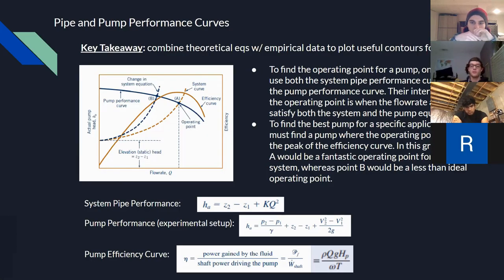To find the operating point for a pump, we must find the intersection of the pump performance curve and the pipe system performance curve. This is the operating point, as at this point both the system and the pump will give the same head rise for a specific flow rate. Once this operating point is found, to find the best pump for a specific flow rate, we must find the pump where the operating point is near the peak of the efficiency curve.